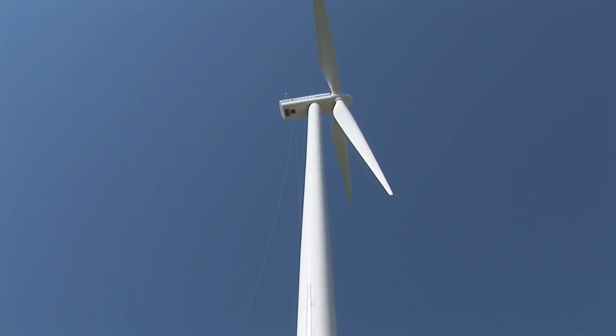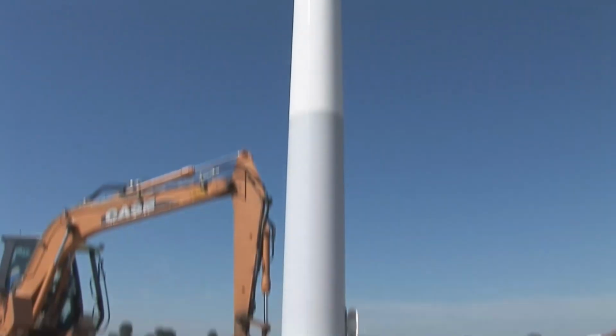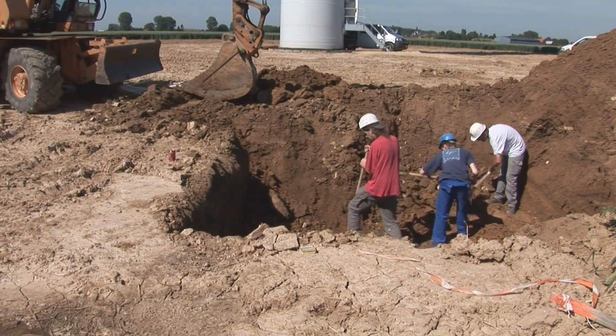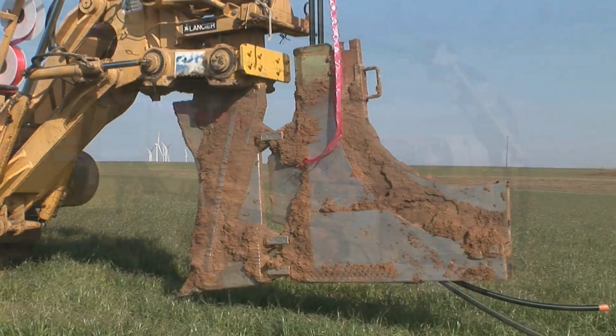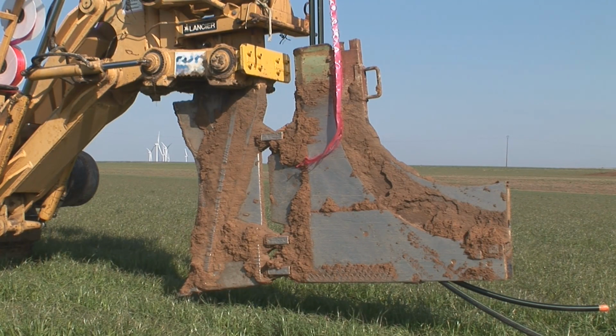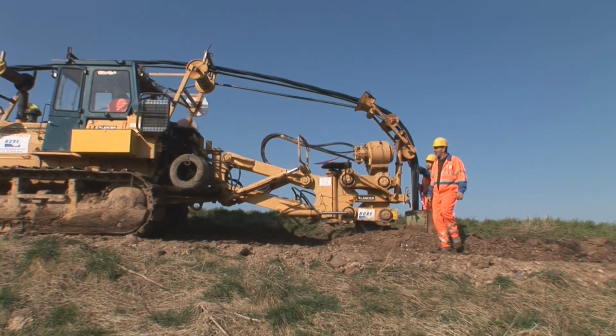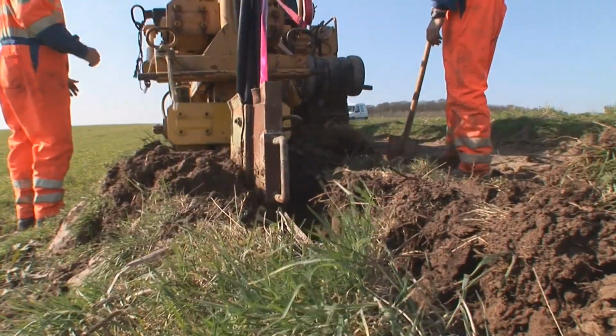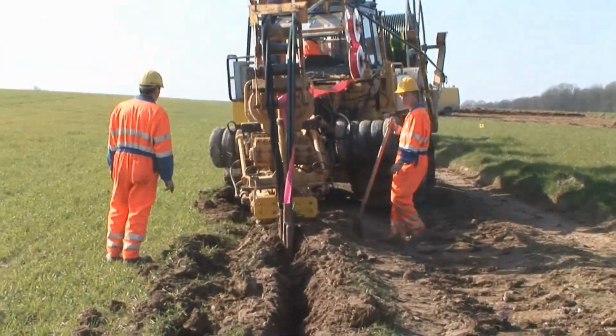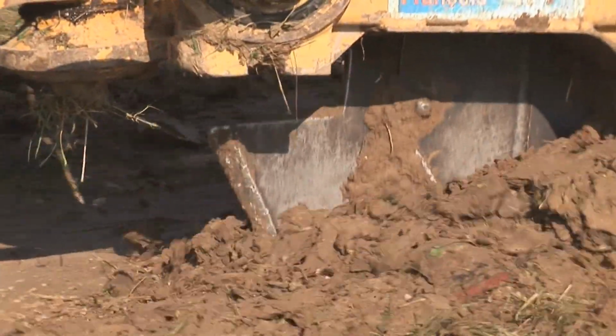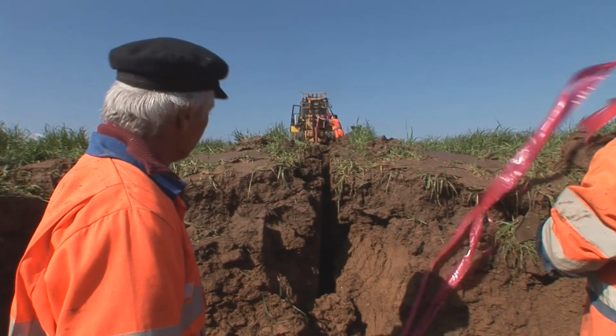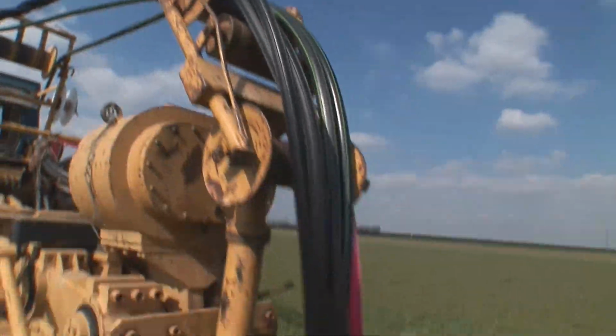But whenever we can, as here, we use the blade. This method doesn't damage the ground, so agricultural land isn't affected because we don't disturb the topsoil or mix in dead earth. The farmer will get the same yields as before we laid the cable. It's also quicker and a lot safer, both for the cable and for the men working around it.